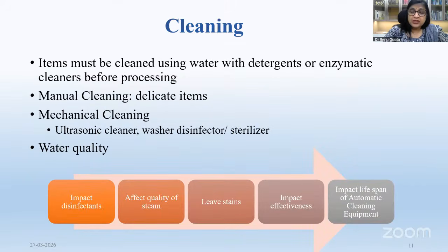After the pre-cleaning of the instrument in the operation theater, these instruments are sent to CSSD. Operation theater is a sterile area. In that, you should not be doing unnecessary cleaning. The cleaning should be reserved to CSSD, but yes, pre-cleaning should be done in the operation theater itself. For the cleaning, items must be cleaned using water with detergent or with enzymatic cleaner before processing.